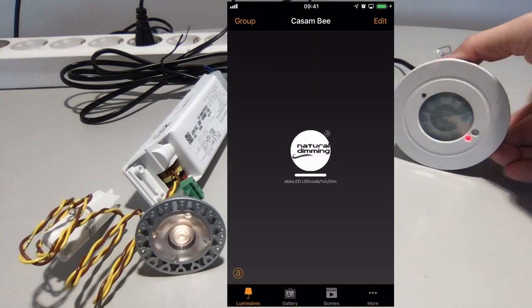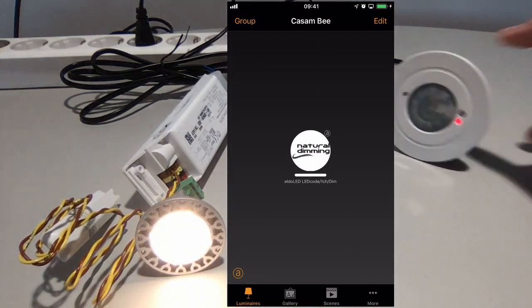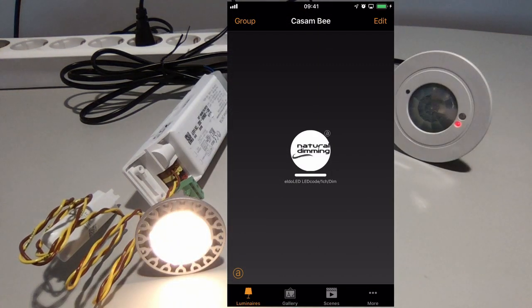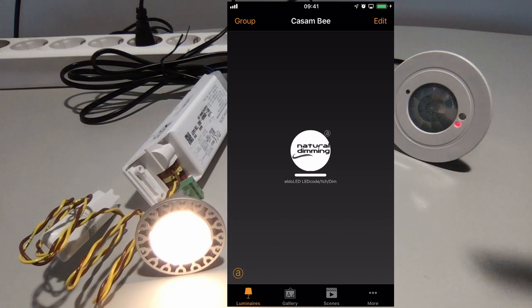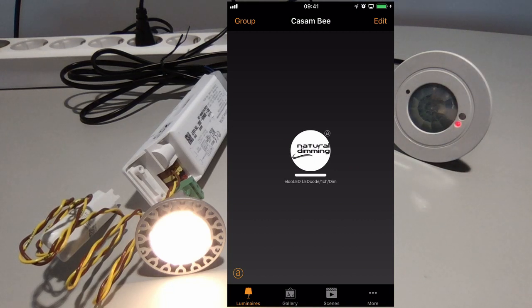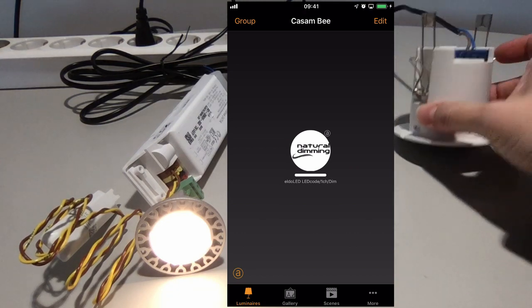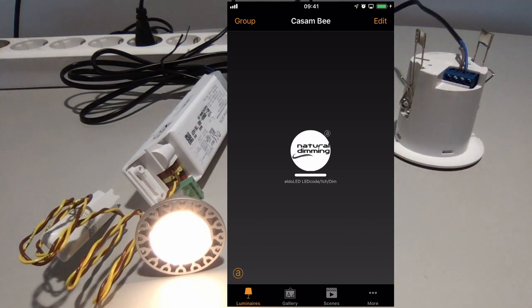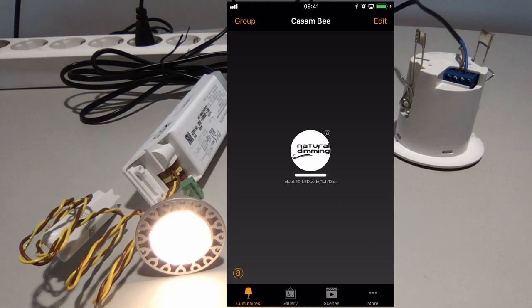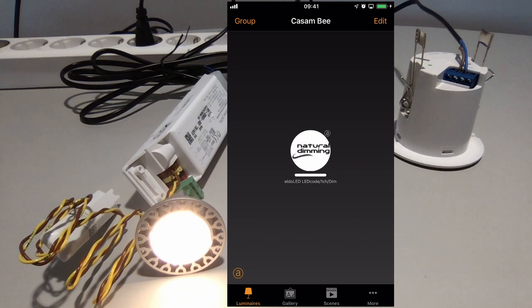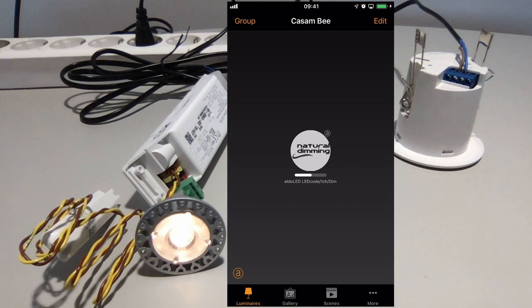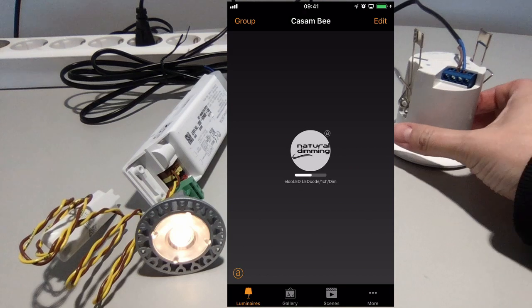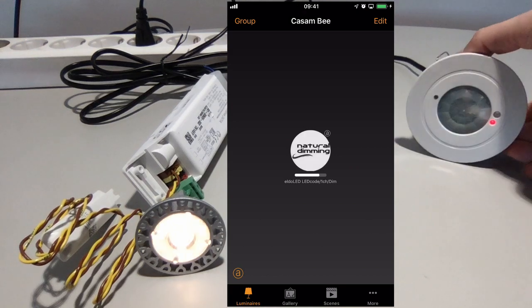If I now trigger the sensor, my presence scene comes on at 100%, and it will stay on until absence is detected. So to create absence, let's turn the sensor back over. The luminaire should now drop to roughly 50%. And now it's dropped to 50%, which is the absence scene. If I re-trigger the sensor, it will go back to 100%.